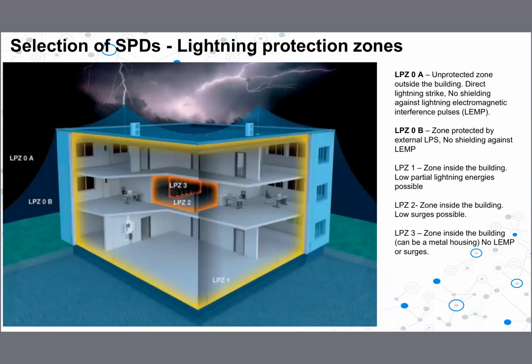So before we go into the selection, we need to identify what lightning protection zones we have. Based on the lightning protection zones only, we decide what type of surge protection device we need to use in our installation. Now in this figure, you can see different types of lightning protection zones. Zone LPZ 0A. This area. Unprotected zone. It is not protected against direct lightning.